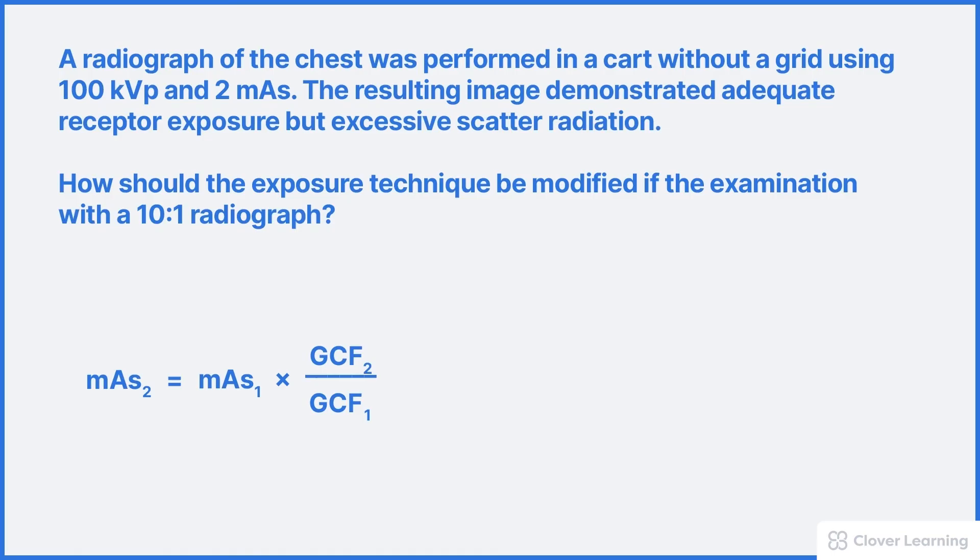This is necessary to ensure the scatter is decreased while maintaining the same receptor exposure. The kVp should not be changed. So we'll start with the formula and insert all known variables. The formula is mAs2 equals mAs1 times grid conversion factor 2 over grid conversion factor 1. The original mAs was 2. The new grid conversion factor for a 10 to 1 grid is 5. The original grid conversion factor for no grid is 1. To calculate mAs2, that's the new mAs, we simply follow the math in the formula. The new mAs, that's mAs2, is equal to 2 times 5 divided by 1 which equals 10 mAs. That's all there is to it. There's no additional steps.